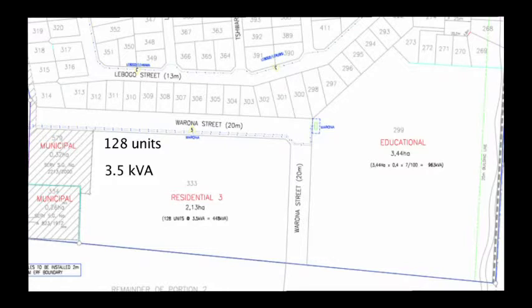So if you do the calculation, as a connection, this is going to need a bulk connection from the utility. We've worked at 128 units at 3.5 kVA, that's 448 kVA. So, City Council, you need to give us 448 kVA to that erf. We didn't look at the FAR here, the floor area ratio, because that was determined by the density. It came out in the wash.